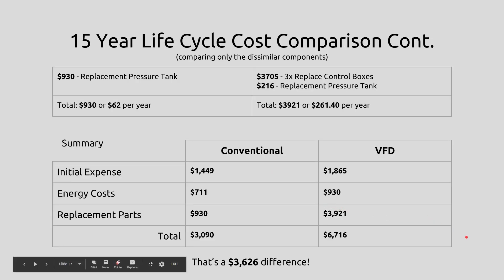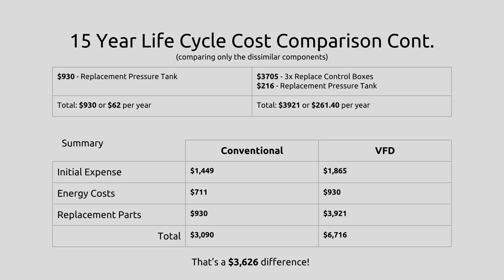Transitioning to the 15-year component wear and lifecycle costs: not a crazy amount of parts here — same as last time: control box, motor, and pressure tank. The 15-year lifecycle cost comparison summarized comes to $930 conventional versus $3,921 for VFD. When we put all that together, we come out with a total of $3,090 for the conventional and $6,716 for the VFD. So once again, in the long run, the conventional system works out to be a whole lot less money.